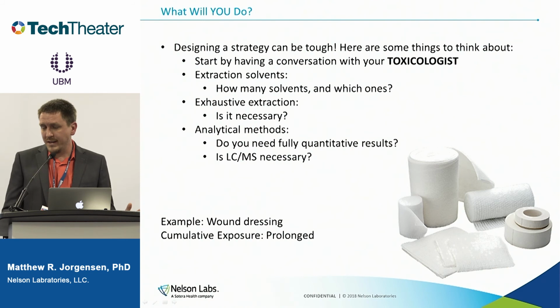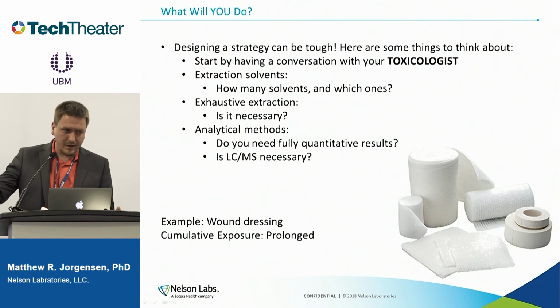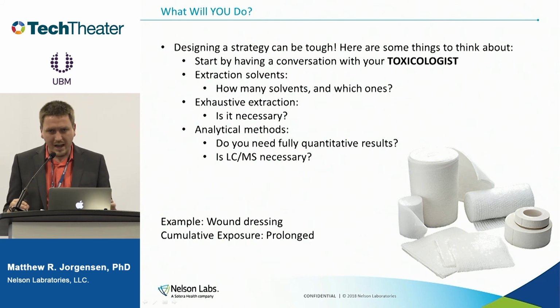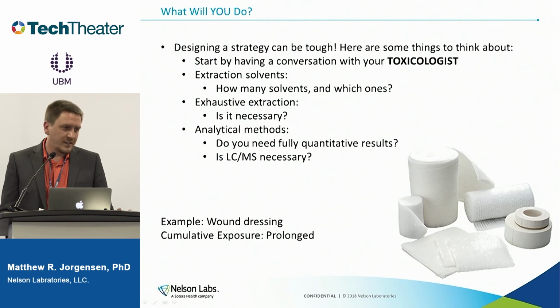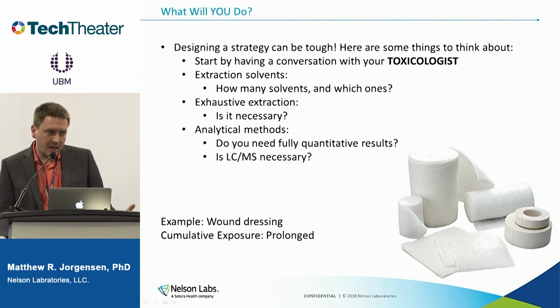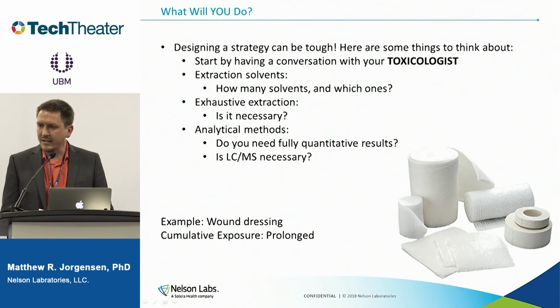And what that means for you is that when the sensitivity is higher, and that means fewer compounds need to be analyzed and reported, it actually can get a little less expensive and easier to do. So the sensitivity comes into play there. For exhaustive extraction, right now we're not really seeing a lot of requests for exhaustive extraction from the FDA unless it's a permanently contacting device. So I don't think we would do it in this case. Probably just use 2 solvents. We'd run the range from water and then do the second one at hexane.